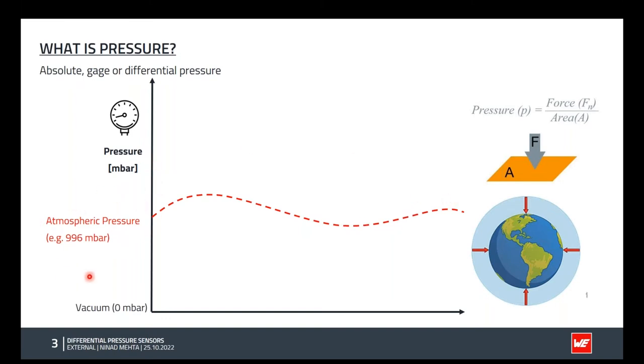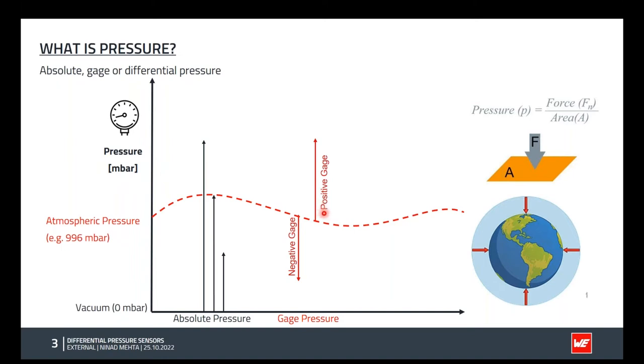When we talk about atmospheric pressure, this is always measured with respect to the vacuum, which is zero. So the atmospheric pressure is an absolute pressure. Absolute pressure is always positive, because it is always referenced to absolute vacuum, or zero referenced. On the other hand, if we take atmospheric pressure as the reference instead of vacuum and then measure the pressure, we can have either a positive pressure or a negative pressure, and this is called a gauge pressure. And the last is the differential pressure, which is nothing but the difference between any two pressures. So it can be positive, negative, or anything. In principle, an absolute pressure can also be called a differential pressure theoretically.